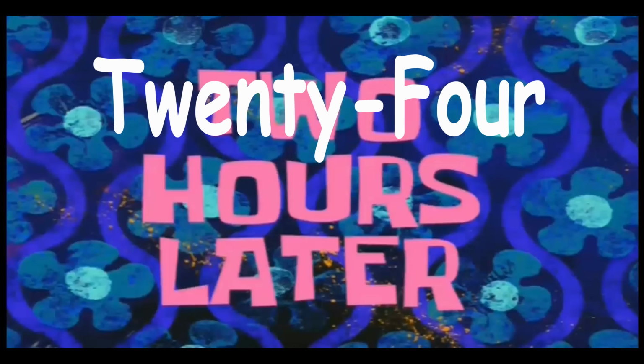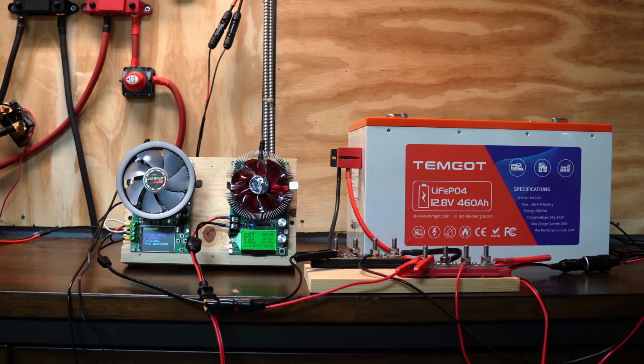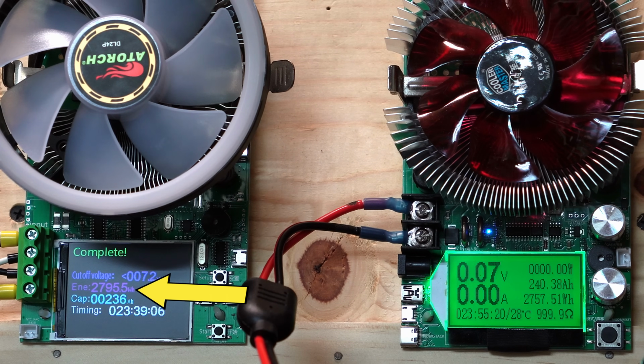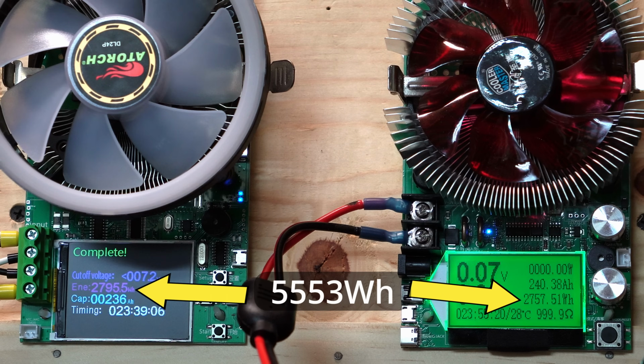Twenty-four hours later. All right, test number 2 is wrapped up. Let's double check the results here. Let me zoom in. On the tester on the left, we got 2,795.5 watt hours. And the tester on the right, we got 2,757.5 watt hours. So that's a total of 5,553 watt hours, out of a rated 5,888 watt hours, for just a little bit over 94% of rated.